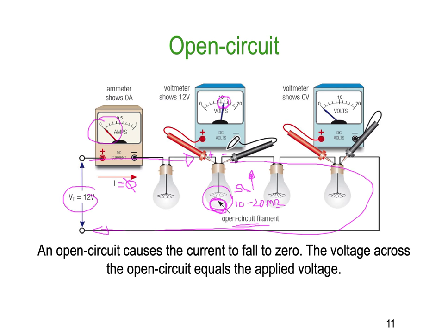So you'll notice that when you're troubleshooting a circuit like this, you've got a series set of lamps. If you get your multimeter out and measure the voltage across each lamp, the lamp that has the fault is the one where the voltage occurs. Nice, easy. Once you understand how a series circuit works and the applied voltage compared to the voltage drops in the circuit, all the lamps that are good, okay, have no voltage. 0 volts. Good lamp, 0 volts. Good lamp, 0 volts. Bad lamp has voltage across it.